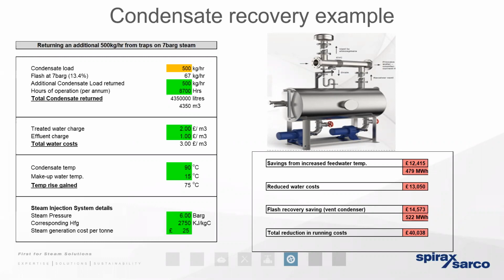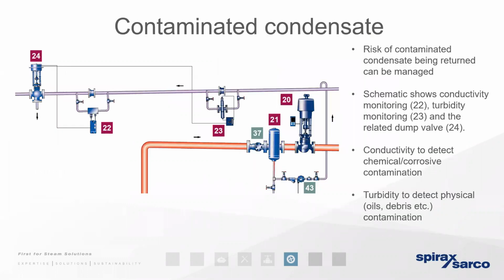Condensate is one of the biggest areas where we can help steam using sites to enjoy cost saving benefits and reduce their energy consumption. We also know that certain processes can be working in areas that can be hazardous. By hazardous, I mean in terms of contaminating the condensate. For example, anywhere that is encountering acids or oils or fats, getting that back to the boiler can have a catastrophic effect on the steam boiler itself.